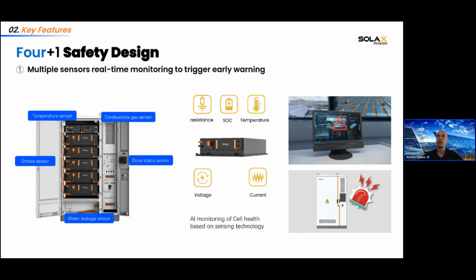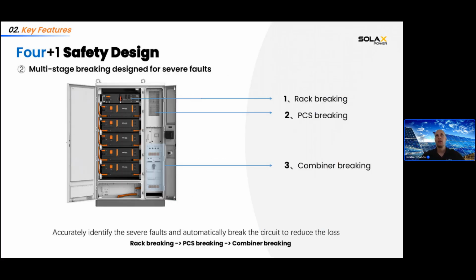And if the battery still has this failure for a longer time, then the second level of safety comes to life, and it will physically switch off the breakers inside the cabinet. The first step would be to switch the rack off, and then the PCS, and then the combiner will be switched off, so you won't be able to use its energy. It will stop working, so it will automatically turn itself off.